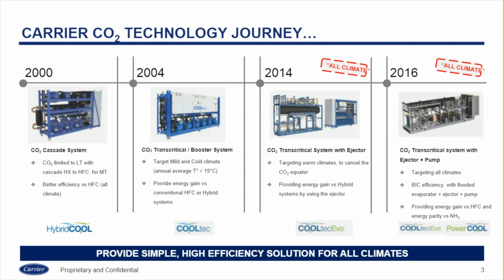Carrier has been a global HVAC and R player in the market for CO2 technology. Actually, we have about 4 technologies. We have the CO2 cascade system applied to introduce it to the market. This is the most common technology we are using so far. We are using CO2 as the low side refrigerant, and for the high side we are using ammonia or HFC. This is targeted to the application or climate application for the system.